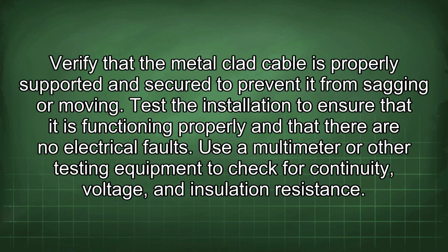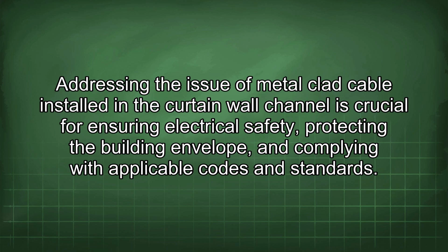Verify that the metal-clad cable is properly supported and secured to prevent it from sagging or moving. Test the installation to ensure that it is functioning properly and that there are no electrical faults. Use a multimeter or other testing equipment to check for continuity, voltage, and insulation resistance. Addressing the issue of metal-clad cable installed in the curtain wall channel is crucial for ensuring electrical safety, protecting the building envelope, and complying with applicable codes and standards.